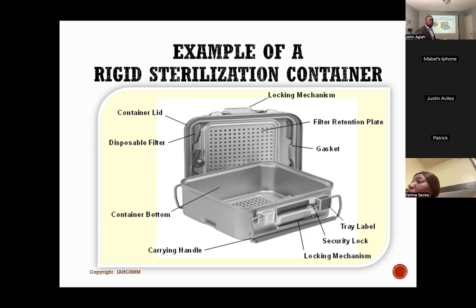So before you use a rigid container, you have to inspect the gasket. Make sure it is not broken. If it is broken, take it out of service and replace it. And the locking mechanism is where we will use our tamper-proof lock to seal it after we are done assembling the tray. We have the container lid, right? That's the lid of the container. Disposable filters go in between the lid and the filter retention plate. That is where we insert the filters.